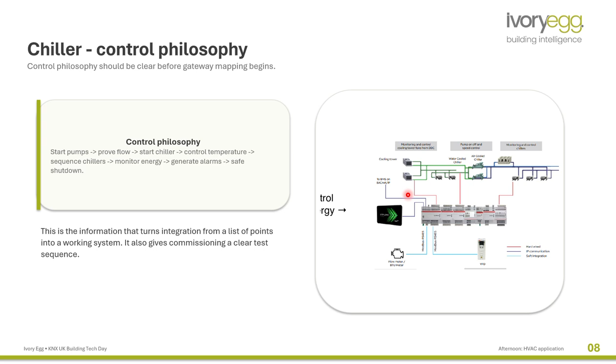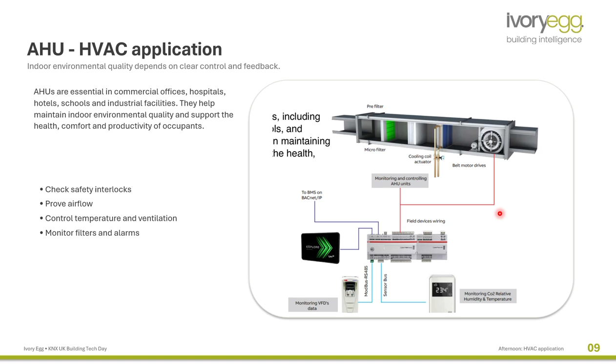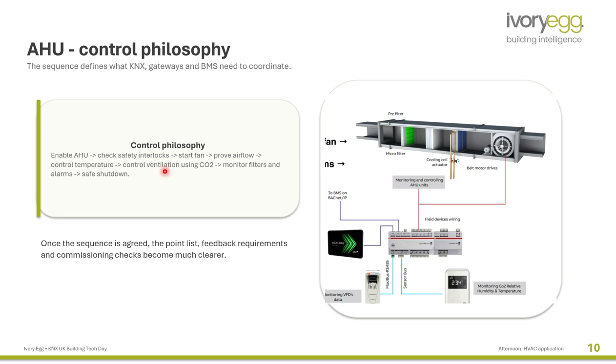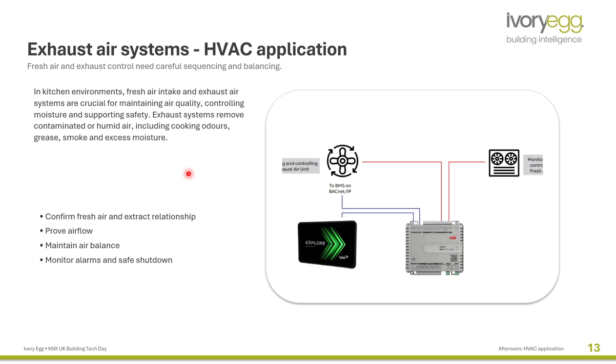In this picture, you can see the primary controller and I/O card next to it. Or for the air handling unit, very popular in building automation. So in the plant room, we should provide the sequence control of the air handling unit. Enable air handling unit, check safety interlocks, all the interlocks. Start fan, prove airflow, everything is coming from the sensors and so on. Control temperature, control ventilation using carbon dioxide, monitor filters, alarms, and safe shutdown. We should be prepared for that in the programming, for the pump and for the exhaust fan and so on. So HVAC control is another complex part of the control in our systems.